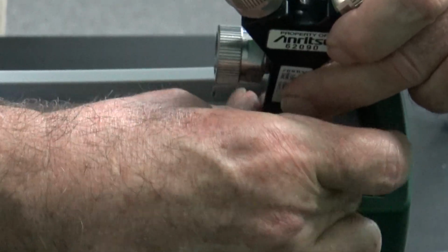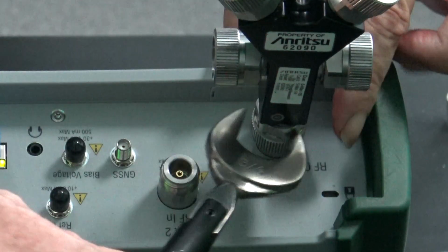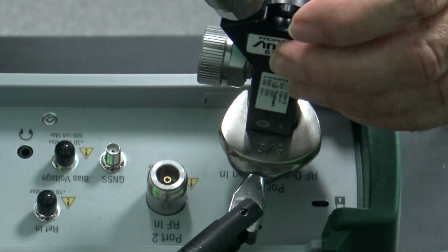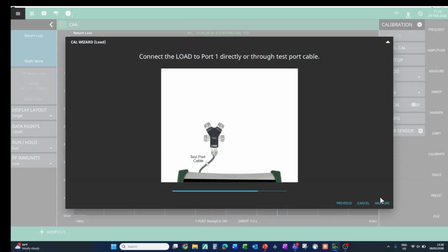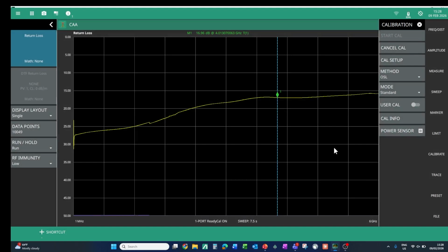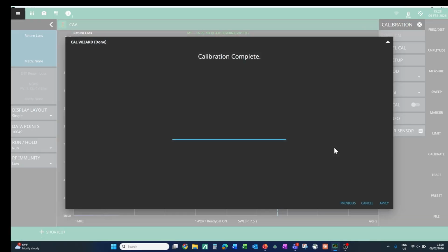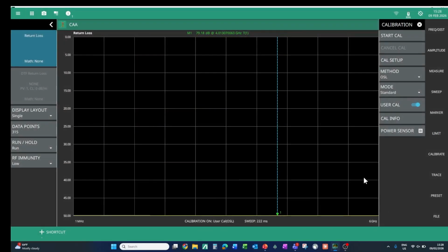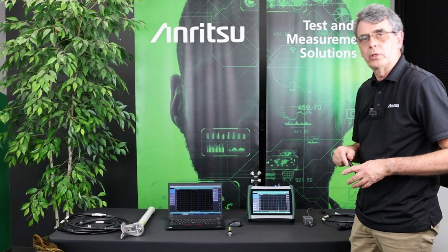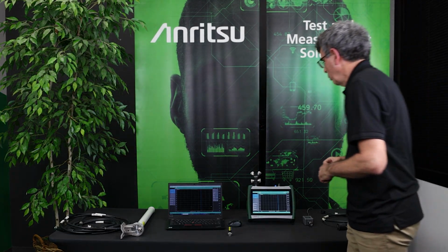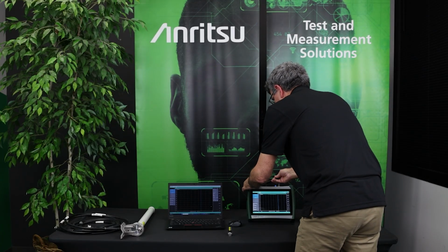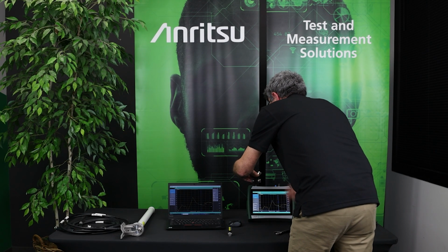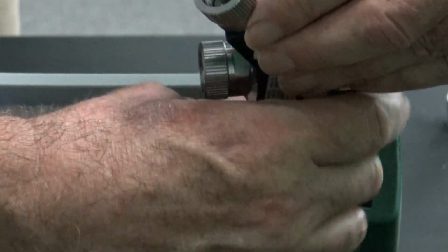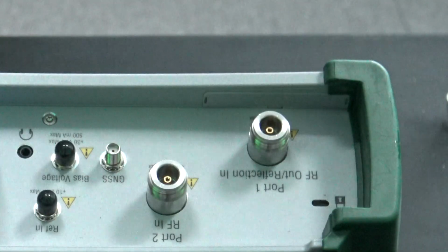So here we are connecting up the load. Here's the torque wrench again. Press measure. That's completed our calibration process. I'm going to apply that calibration data. Now, because the same load is still connected to the test port, that's the load that was used for the correction coefficient. So that is going to give us like a perfect return loss. So let's connect the load that we looked at before and compare the return loss we measure on our precision load.